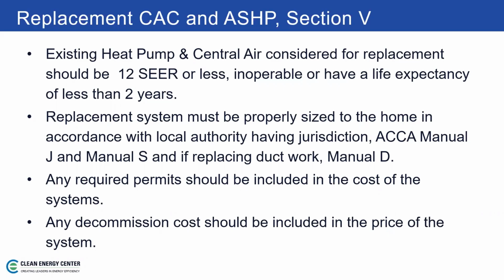Got a question when dealing with the issue of R22 refrigerant. If the unit is a functioning unit but has a leak and uses R22 refrigerant, are we replacing the system or attempting to repair the system? I think maybe this is close to what you were just talking about. I apologize for reading the whole question, but I hadn't gone through it yet. Use the more costly R22. And really that has to be a judgment call too, Jack, right? To me, if you're dealing with a system that's that old, and you've got R22 refrigerant and it has a leak, if you fix it, it's probably going to get another leak pretty soon. You should be looking at that as an opportunity to replace the system.